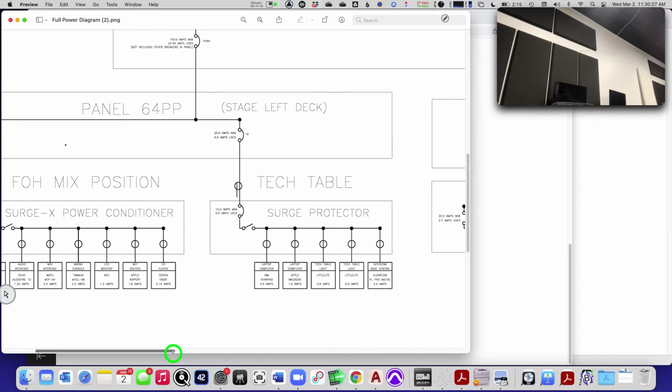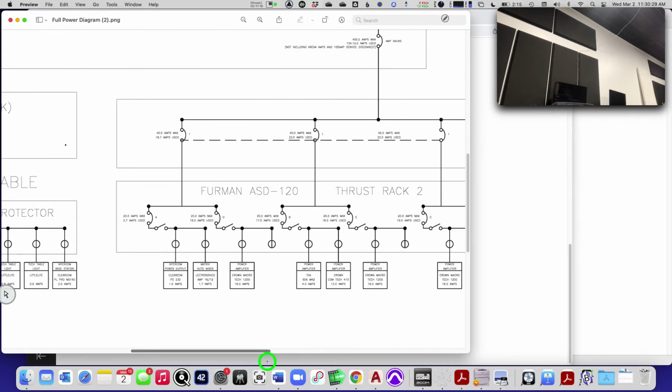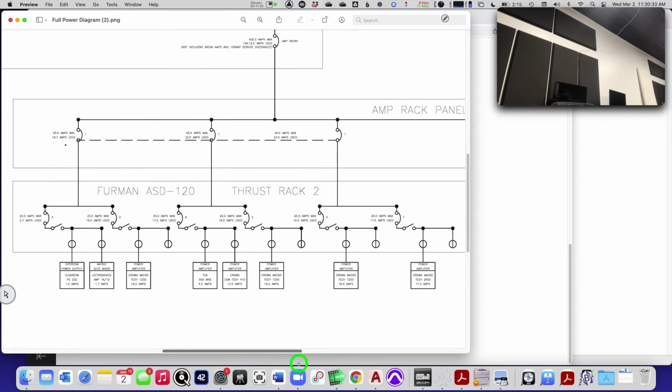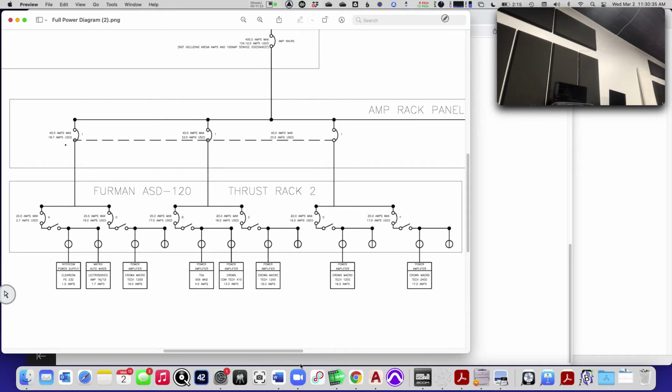Okay. This is a special thing. This is a sequencer. Remember the thing I told you where you sequence it on and off? Here the sequencer has 6 20 amp circuits built into it, and they are attached, in pairs, to 40 amp breakers, which should be fine, right?